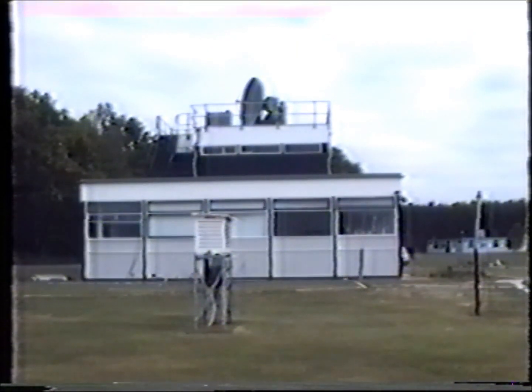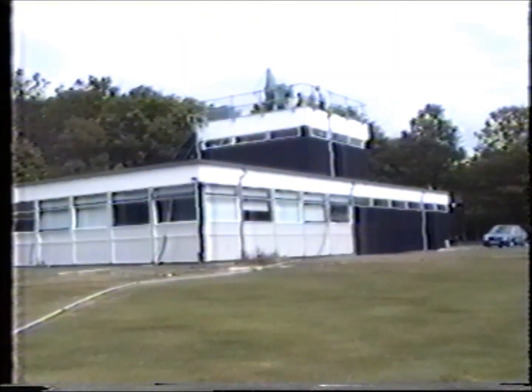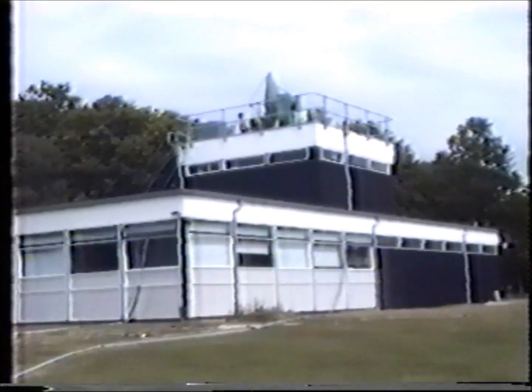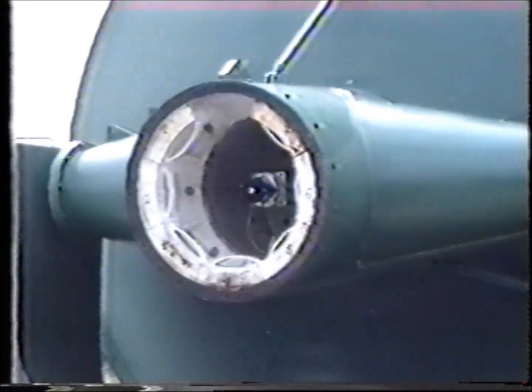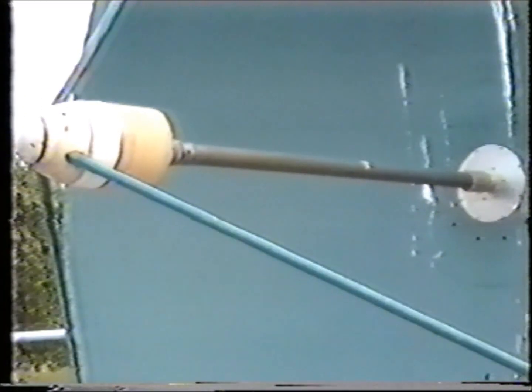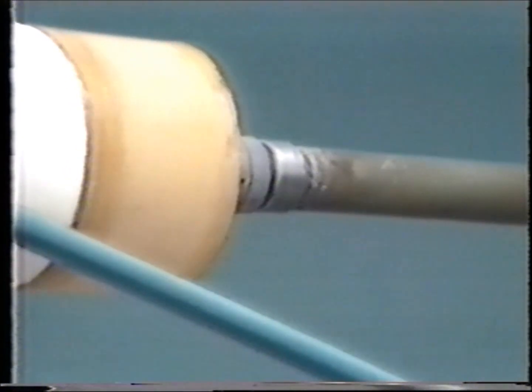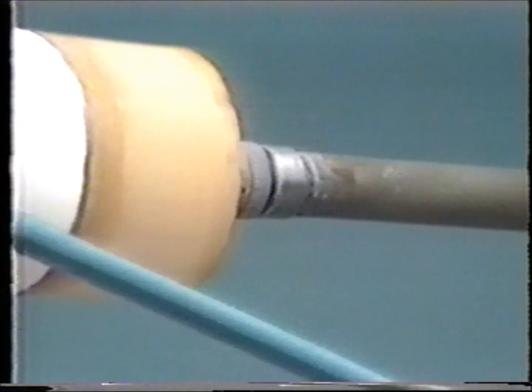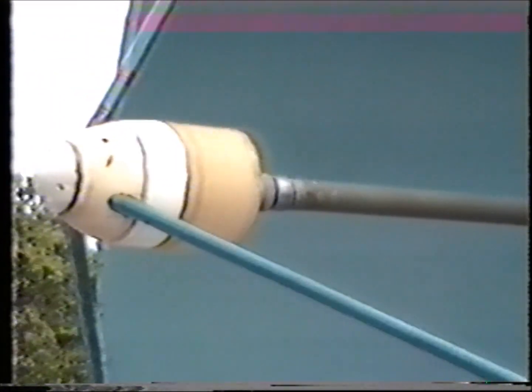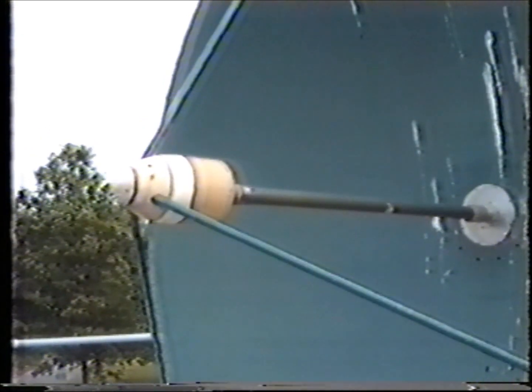One of the more unusual jobs of the Quality Assurance Lab is that of radar dipole calibration, a very pleasant task in good weather. The dipole is part of the aerial assembly and transmits pulsed electromagnetic radiation in a narrow beam onto the radiosonde reflector. The dipole rotates and provides positional information to the aerial control system so that it is capable of locking on and following the moving target.